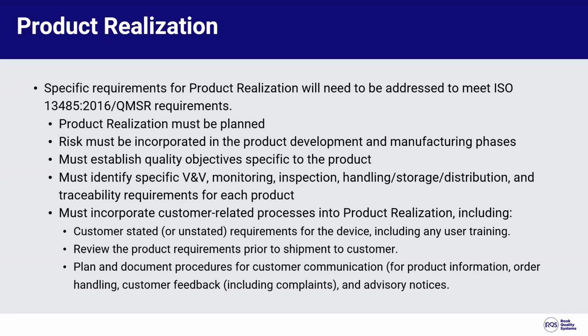There's also specific requirements for product realization that need to be addressed to meet ISO 13485 and QMSR requirements. So product realization is something that is more like the beginning steps of your design and development. It's not explicitly called out within the QSR currently, while there's tons of information within 13485. So for product realization, they talk about how you have to incorporate risk into product development and manufacturing phases. You have to establish quality objectives that are specific to the product. You have to identify specific verification, validation, monitoring, inspection, handling, storage, distribution, and traceability requirements for each product.